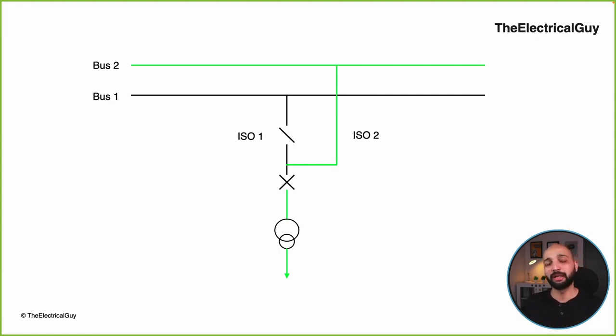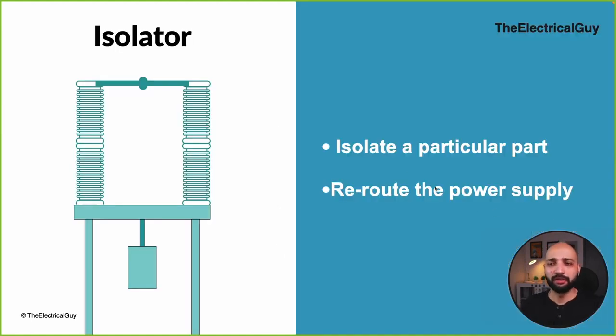Of course it can be done, but a circuit breaker is an expensive device compared to the isolator. Isolator is a very cheap option available. So definitely isolators are preferred for this purpose. So the function of an isolator in a substation is to isolate a particular part for maintenance activity and also to reroute the power supply. This is really important, and please do remember.